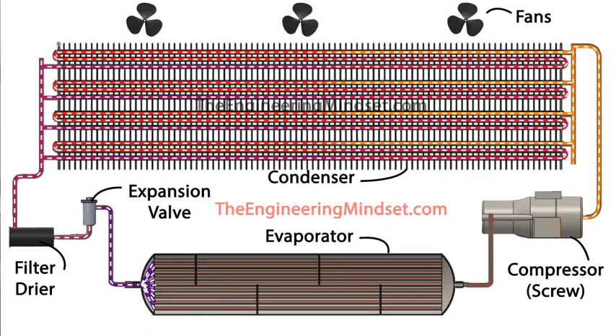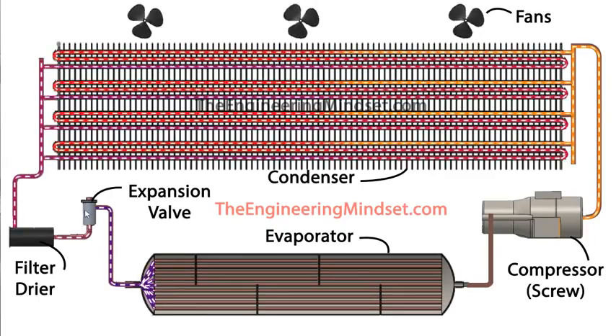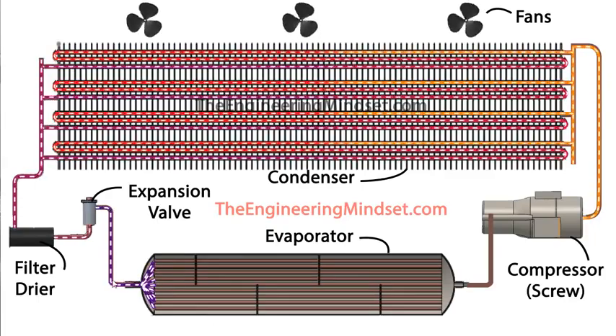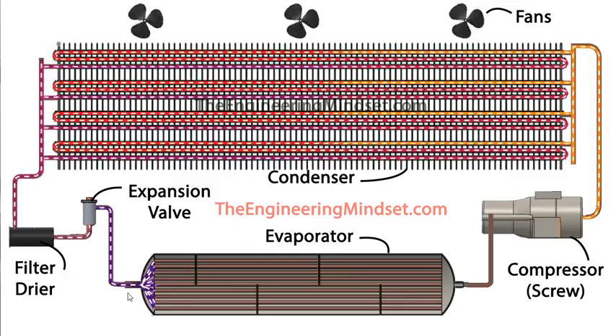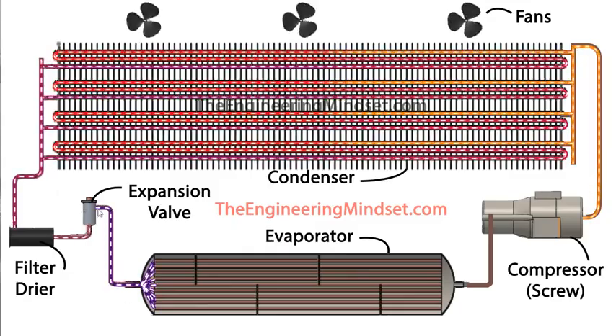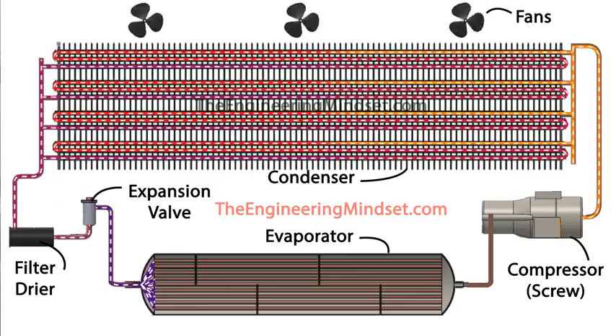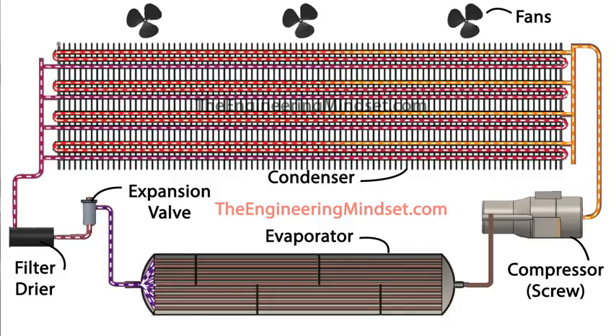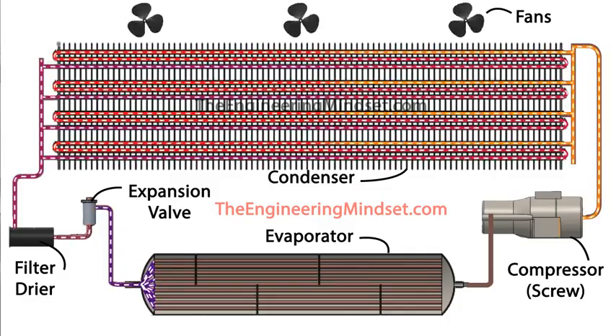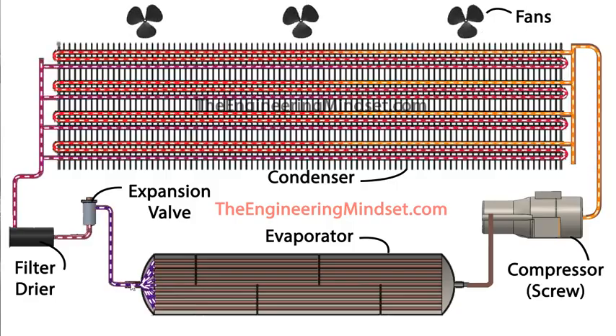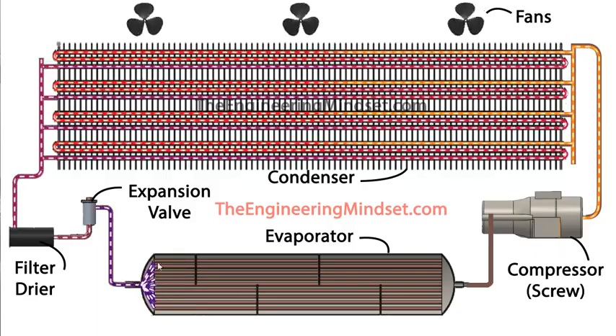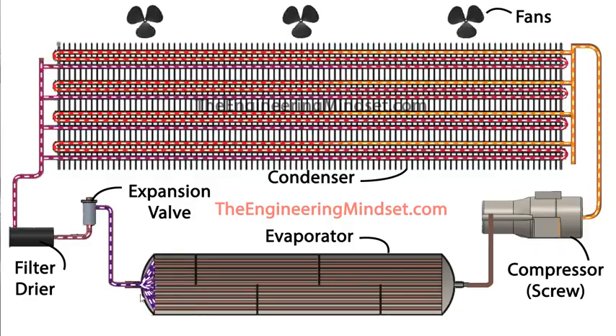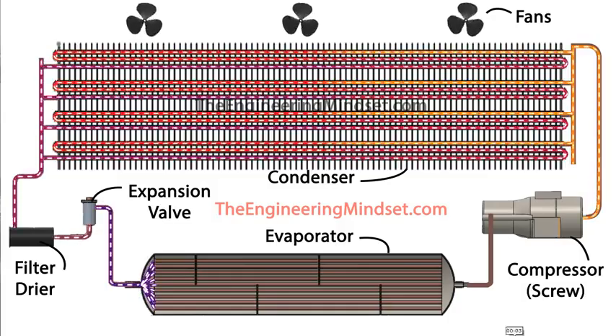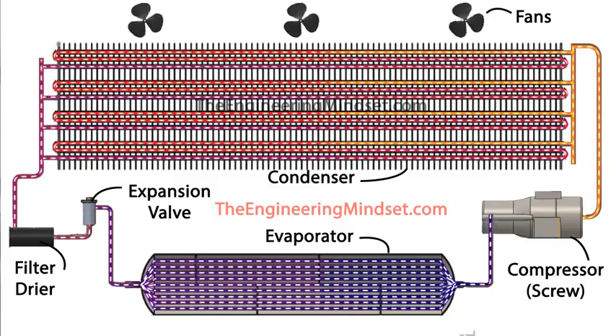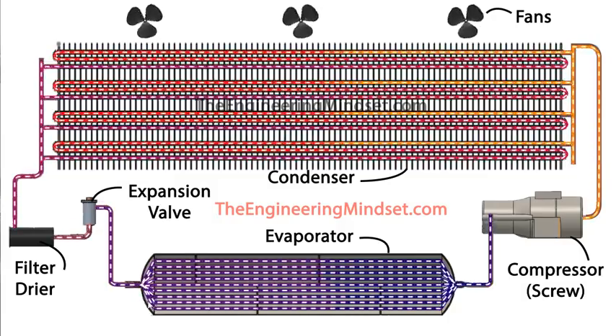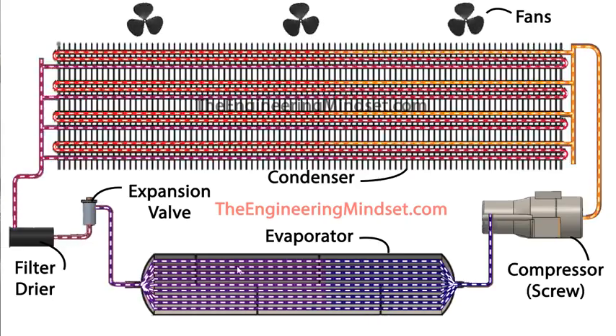But anyway, the refrigerant will then leave the expansion valve, and that will make its way off into the evaporator. Now the refrigerant here, as it leaves the expansion valve, is going to be a low pressure, low temperature liquid vapor mixture, and that will then come into the evaporator. It will spray into what's called the water box, but there's refrigerant inside it, and the refrigerant will then split apart and enter these different tubes.